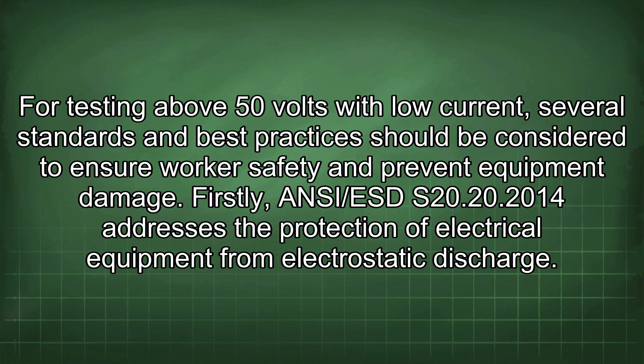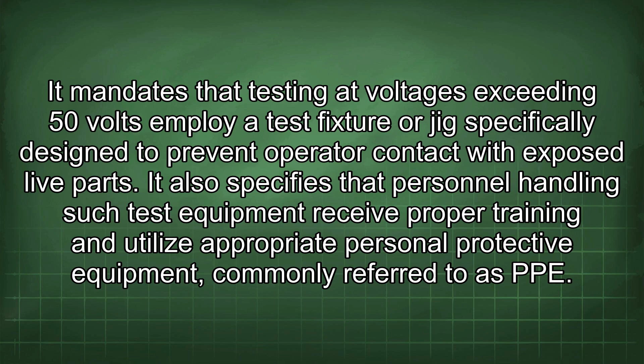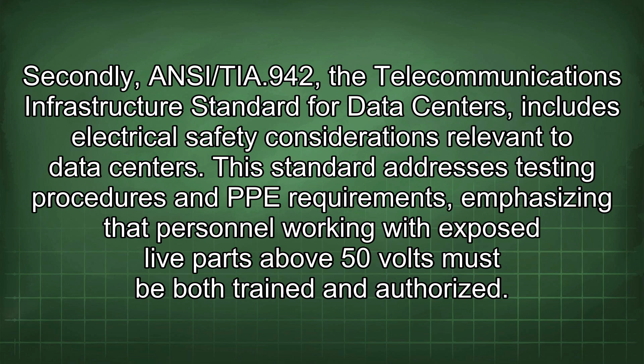It also specifies that personnel handling such test equipment receive proper training and utilize appropriate personal protective equipment (PPE). Secondly, ANSI/TIA 942, the telecommunications infrastructure standard for data centers, includes electrical safety considerations relevant to data centers. This standard addresses testing procedures and PPE requirements, emphasizing that personnel working with exposed live parts above 50 volts must be both trained and authorized.